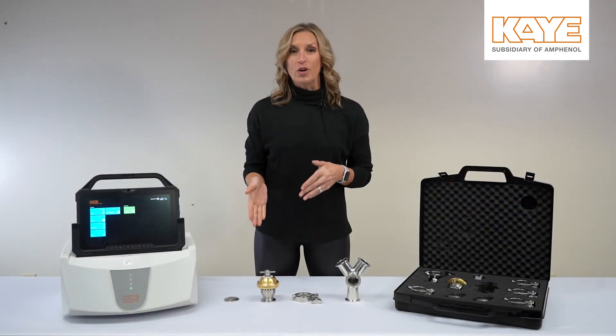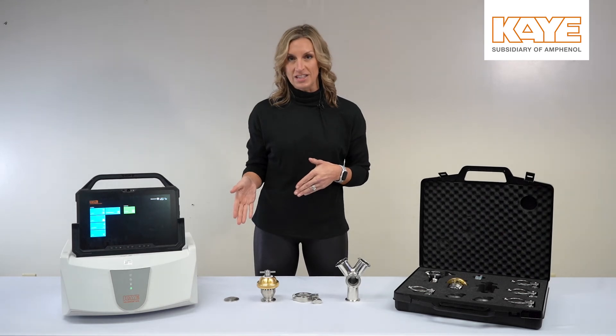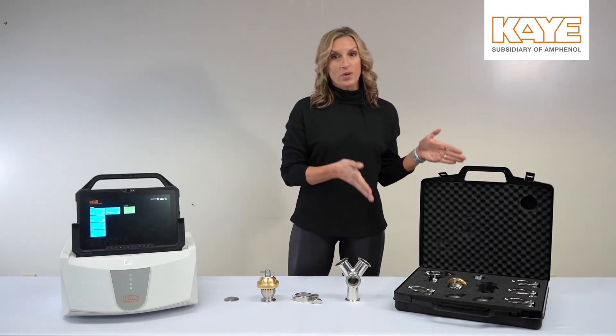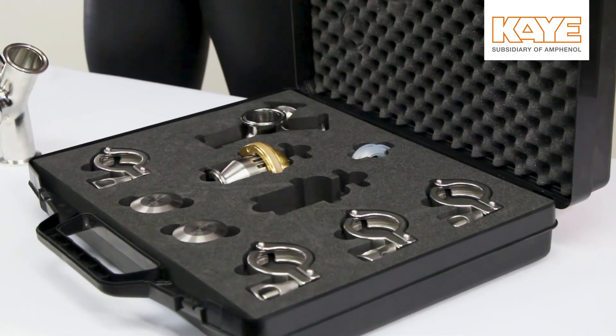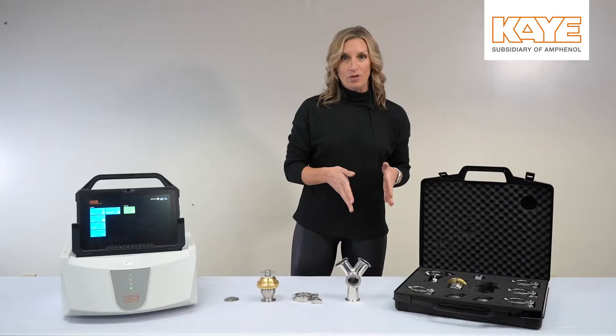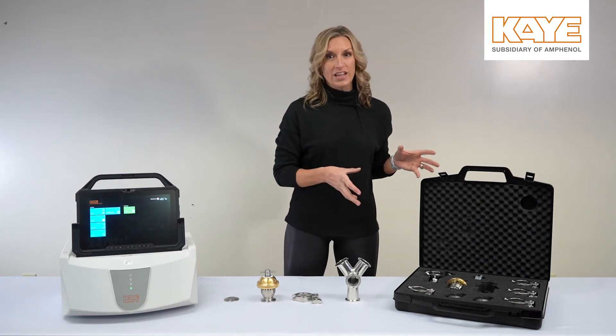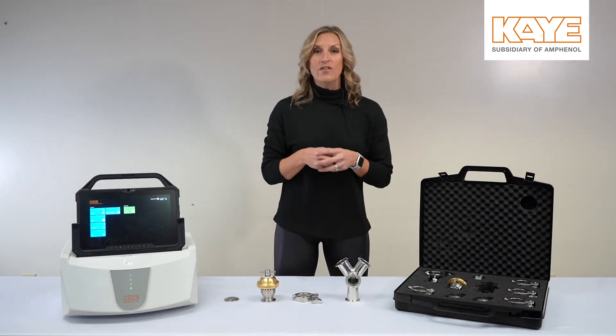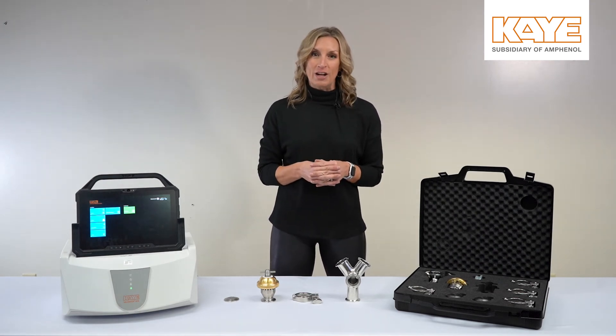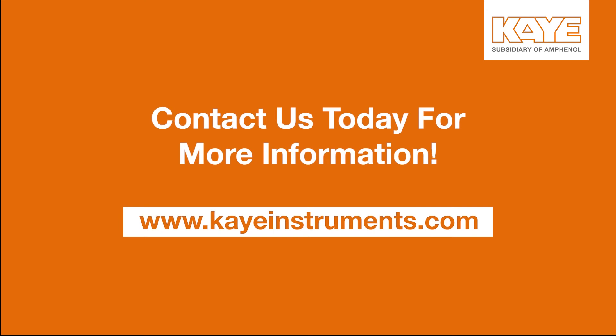With the Kaye Feed-Through, you have a great way to feed your thermocouples into your autoclave to run a validation study. With the Feed-Through Kit, you have the ability to add not only 18 thermocouples but up to 36, and also add a pressure transducer — it's really everything you would need for an autoclave mapping. If you have any questions, feel free to reach out to your local account manager or visit us on the web at www.kayeinstruments.com.